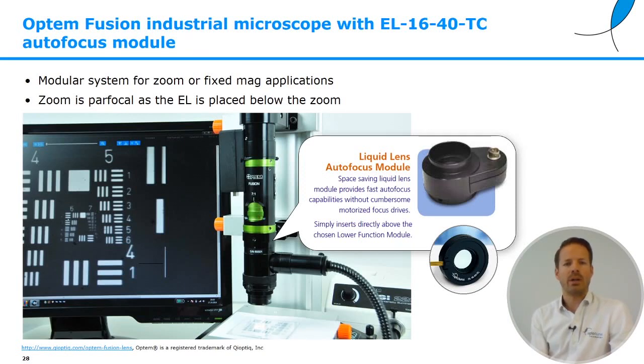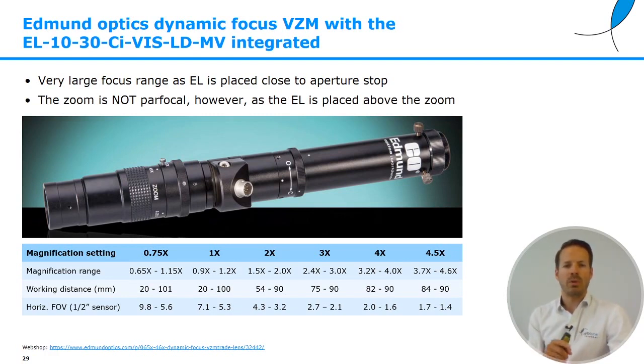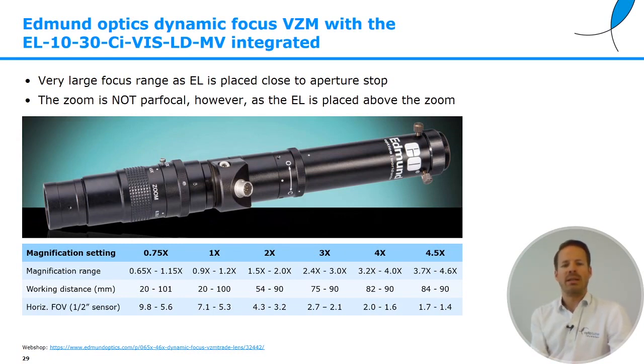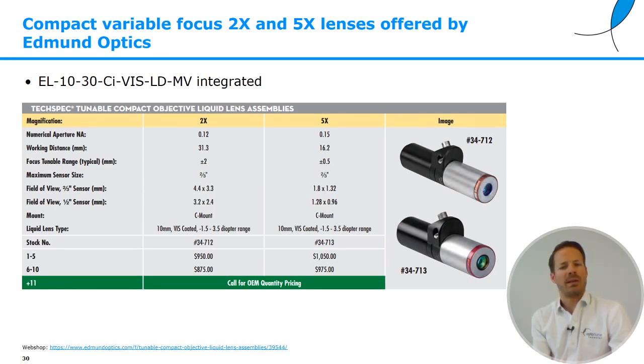A similar system from Qioptiq, the Optem Fusion, also has an autofocus module with the EL16 designed in. Edmund Optics has a variable zoom lens with an EL10-30 integrated above the zoom, which means this system is not parfocal — after zooming you will usually have to refocus. It provides magnifications of 0.75 to 4.5x. Edmund Optics also has compact 2x and 5x lenses with the EL10-30 integrated in the middle — very useful for a compact portable system that doesn't need zoom, and fairly well-priced, making it a good solution for OEMs, though a bit less versatile than the modular solutions.